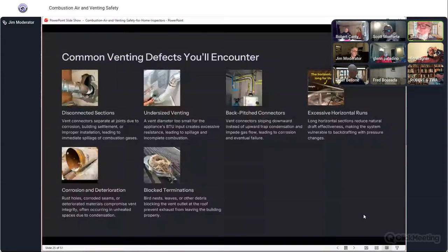But isn't that so? I used to argue that. Then I thought it out a little bit more. Doesn't that water heater run by itself in the summer? And we may not have that problem in the summertime? Or is it able to use that chimney by itself in the summer because the temperatures are different? It's warmer outside. I don't have the answer, but I used to say, well, the furnace doesn't run in the summer and the water heater is fine all by itself all summer, before they change that furnace out. So it's colder. I made it a practice to call that out all the time, just in case.